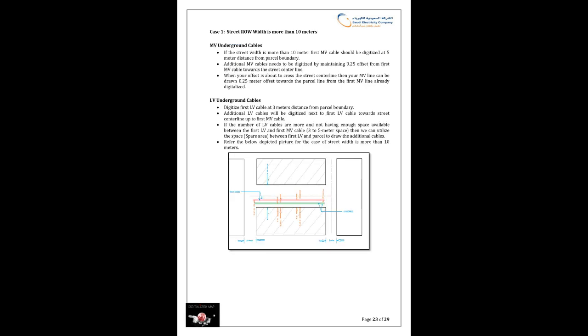Case 1. Street ROW width is more than 10 meters. MV underground cables. If the street width is more than 10 meters, the first MV cable should be digitized at 5 meters distance from the parcel boundary. Additional MV cables need to be digitized by maintaining a 0.25 offset from the first MV cable towards the street center line. When your offset is about to cross the street center line, then your MV line can be drawn at a 0.25 meter offset towards the parcel line from the first MV line already digitized.